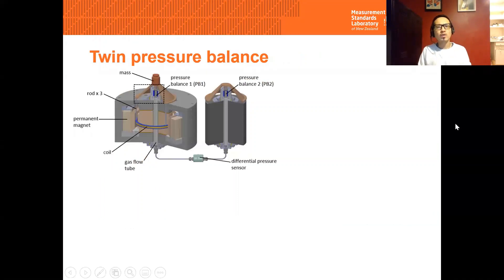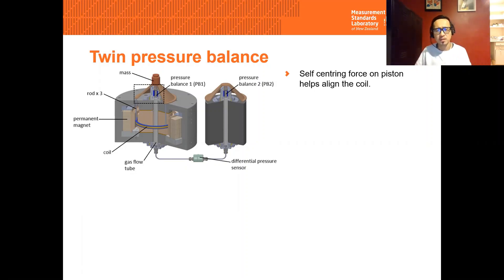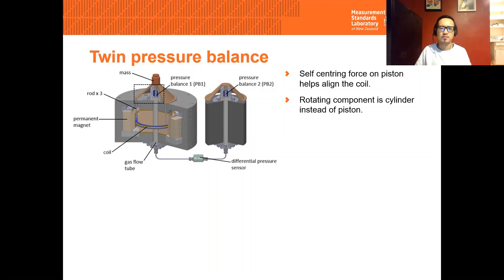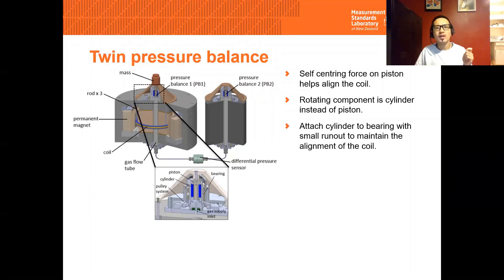One of the reasons we use a twin pressure balance design is to simplify the alignment for our Kibble Balance. This relies on the self-centering force on the piston to help align the coil with the magnetic field, remembering that the coil is attached to the piston. For most conventional pressure balances, the piston is the rotating component. However, in our Kibble Balance, we cannot rotate the piston because the coil and other components are attached to it — if it rotates, it will fall apart. So we have to rotate the cylinder instead. We are assembling a setup where the cylinder is attached to a smooth bearing with small vertical and angular runout to ensure the alignment of the coil. The cylinder has to rotate at least 0.5 Hz for the self-centering force to take effect.